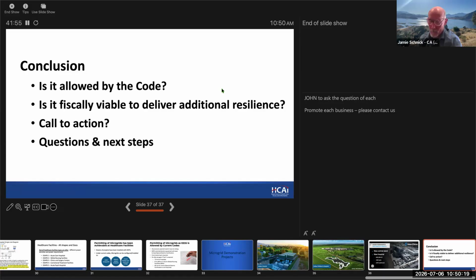Sorry to interrupt, because I think we're going to get asked this question if we go down this pathway. If the implication is that the hospital can operate in the emergency mode with the fuel cell, then the fuel cell is on the normal power side of the ATSs. You have two problems. You either can't operate during an emergency because of anti-islanding provisions of Rule 21, or you have to have some kind of secondary disconnect from the utility that allows you to be mechanically islanded. Otherwise, that's not going to be allowable.